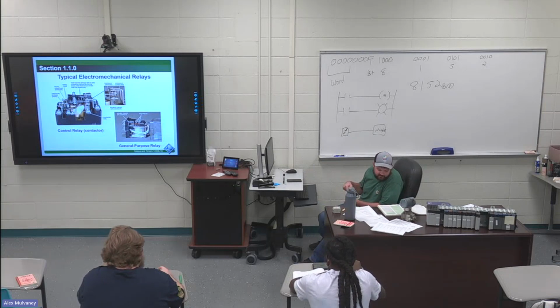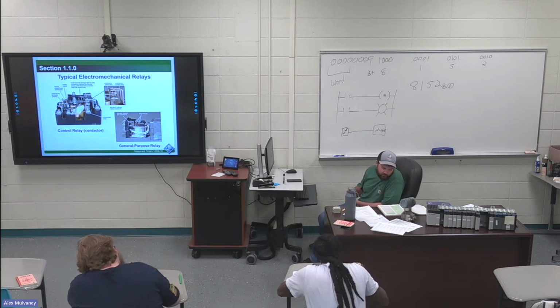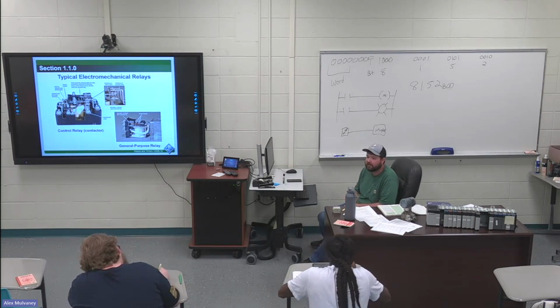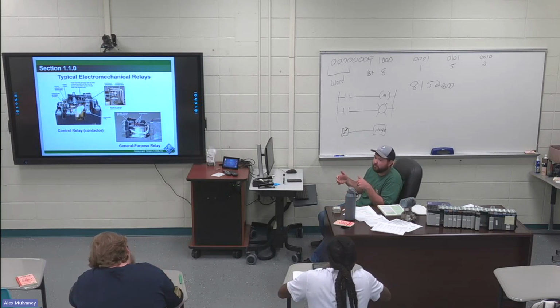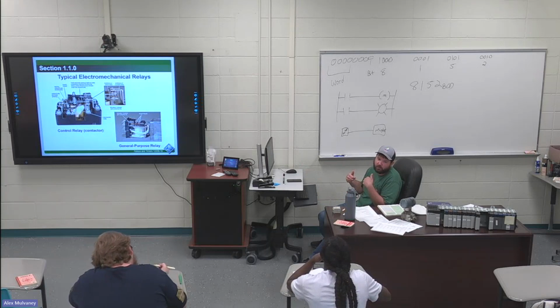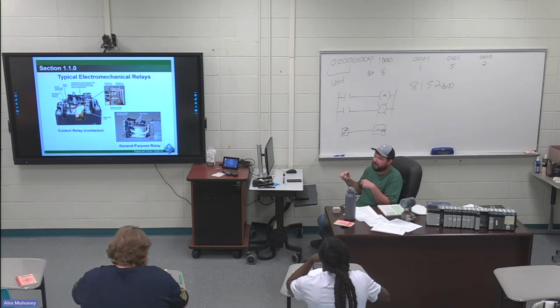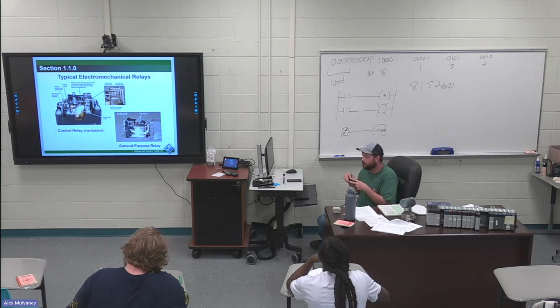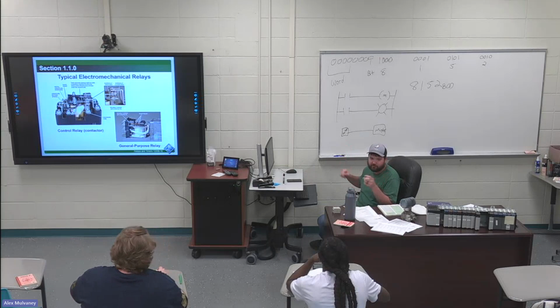My first highlight is the first sentence on the page. A relay is defined as an electrical or mechanical device used for remote or automatic control of other devices or systems. Usually what you're using a relay for is you're controlling a relay at a lower voltage and controlling something or turning something on at a higher voltage, or you're multiplying your effect. If I turn a relay on, I can turn on or off several different things at once. So there's a couple different purposes for a relay.